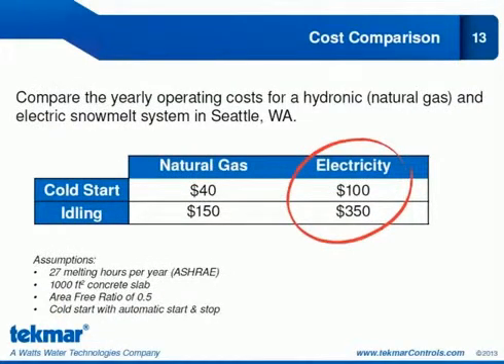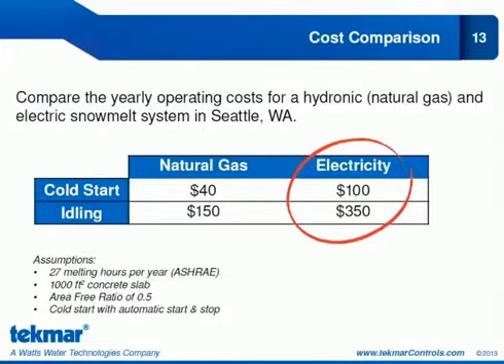Another cost comparison looks at Seattle, Washington, where ASHRAE data shows only 27 melting hours per year. Even though natural gas is still cheaper — $40 for natural gas versus $100 for electricity on a cold start — the overall operating costs with electricity are so low in a climate like Seattle that you're probably not going to see a return on investment by going with a hydronic system. In a low-melting-hours climate like Seattle, you would probably want to install an electric snow melt system.